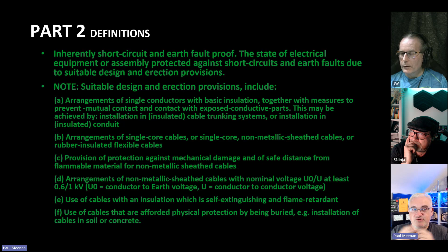So for instance, when you do a PFC reading, let's say you're at Mrs. Jones's house, the PFC is 6.2 kA. Oh no, let's go 10 kA, and she's only got 6 kA breakers. You could argue that's not inherently short circuit and earth fault proof. Where that fits in the regulations, though, I don't know. But I like the statement and the definition. So I actually hope that stays. I hope that stays. Because I mean, that's assuming that we're talking about all of the equipment.